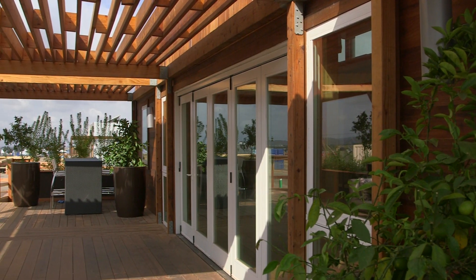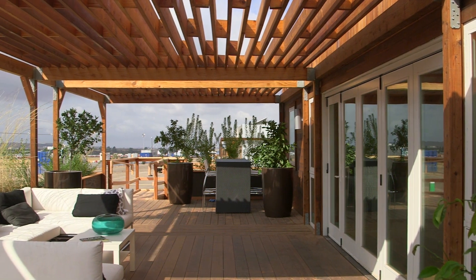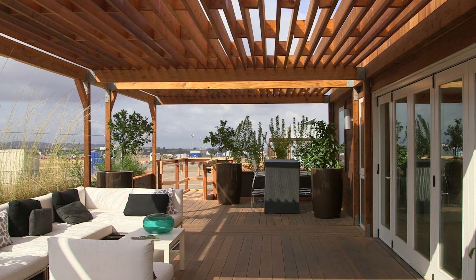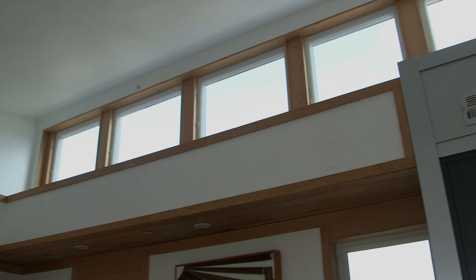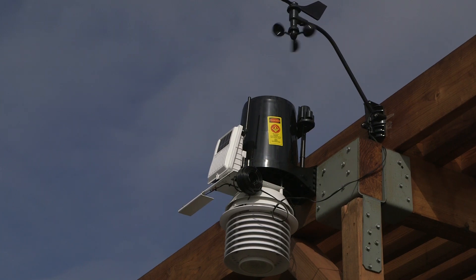Along the back deck we have a pergola that shields the southern face of the house from getting beat down by the sun all day, and that really helps cool the interior. We have some track windows low down on the south side that open up on mechanical actuators, and the north clerestory windows open up. Our control system senses when there's a favorable temperature difference between interior and exterior, opens up those windows, and we have a small stack cooling effect.